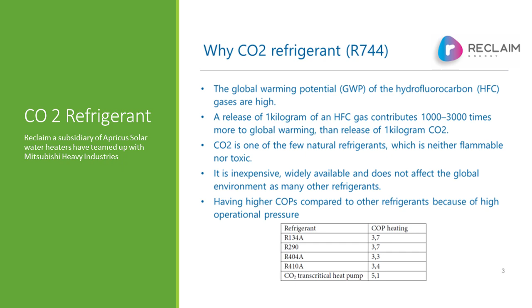I'm sure everyone here would know what COP is. Anybody not? Yep, a lot of people don't. Okay, so basically COP is your coefficient of performance - the amount of energy effectively you're accumulating from the environment and giving to the water. So if you've got a COP of 5, with a 1 horsepower, 1 kilowatt system, you're putting 5 kilowatts of energy into the water. It's equivalent of a 5 kilowatt heating element, even though it's only drawing a single kilowatt. The reason it can do that is that it's extracting heat energy from the air or from the sun. It's the same principle used in reverse cycle heating, which typically has a COP of 3 or so.